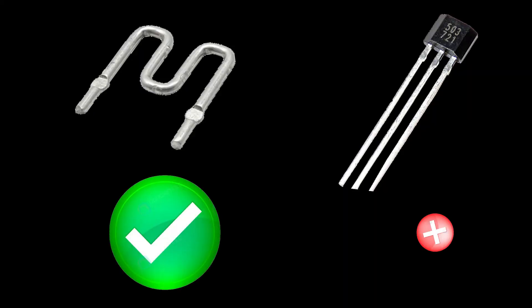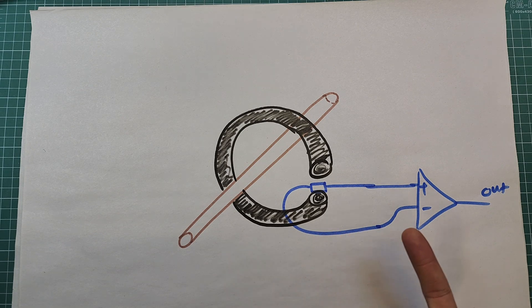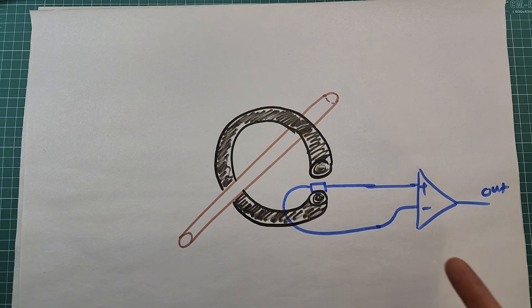This method also has its disadvantages. The main one is that its accuracy is lower than that of the shunt resistor method. It also needs to be calibrated and is affected by external magnetic fields — if a magnet gets close to the sensor, it will disturb the entire current measurement system. Some of these disadvantages can be compensated by small changes in the circuit. The circuit described so far is called an open-loop circuit; there is another model called a closed-loop circuit.